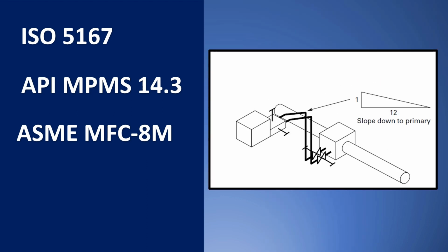Similarly, how should the transmitter be installed? For gas service, it should be above the tapping. There should be a certain slope towards the pipe, so because of gravity, if there is any liquid, it will fall back into the pipe. All of these amazing things are covered in this standard. And this MFC stands for measurement of fluid in closed conduit.